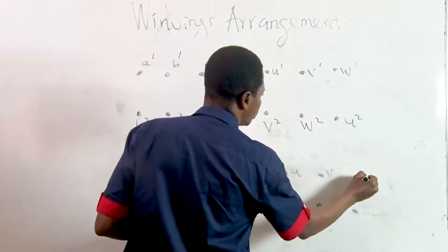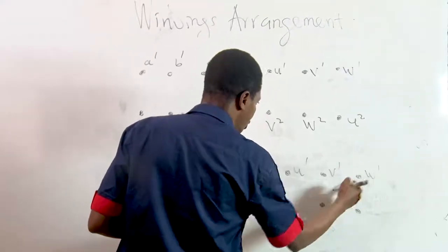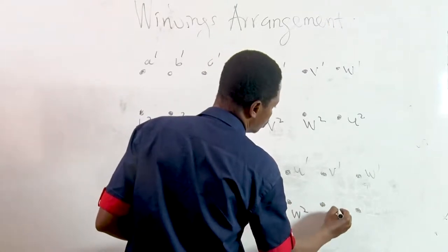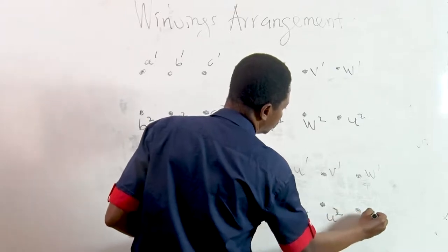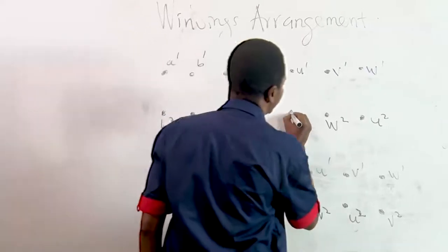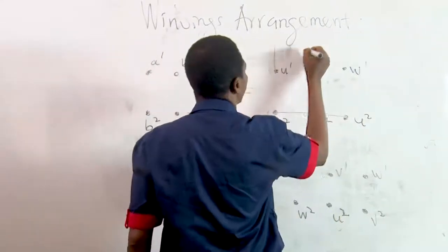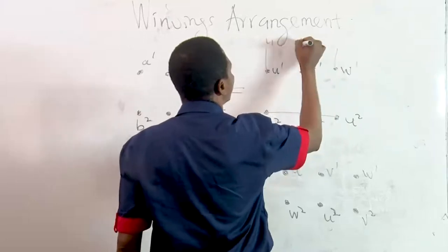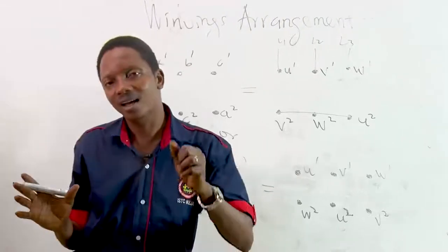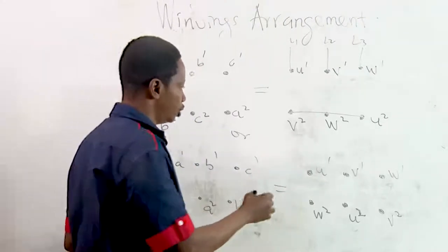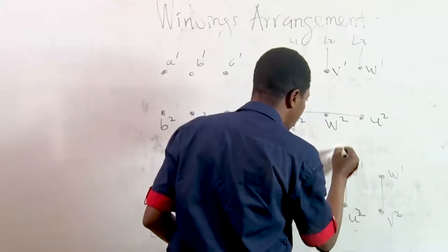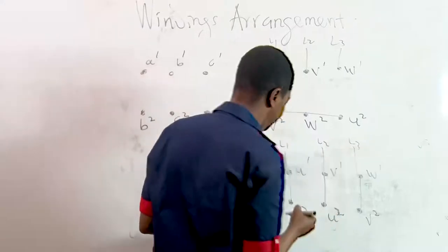So, this equals U, V, W, 1, 1, 1. I'm now using W, then this will be W2, U2, and V2. Now, let me start with the first one, star, and delta the second one. To start it, you link the three, and then you power it with line 1, line 2, line 3. This is the conversion of electrical energy to mechanical energy. For delta, you link up and down together. I have line 1, line 2, line 3.